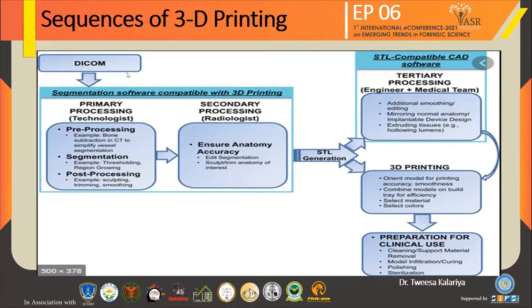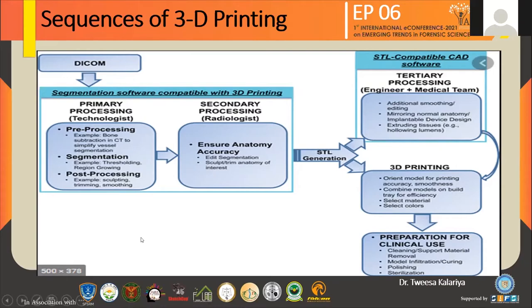STL compatible CAD-CAM software: the necessary process is done by the engineering or medical team, including additional smoothing and editing, mirroring the normal anatomy, implantable device design, and extruding tissues such as hollowing the lumens. 3D printing steps include orienting the model for printing accuracy, smoothening, combining the models on the build tray for efficiency, selecting materials and colors, preparation for clinical use, cleaning and support material removal, model infiltration, curing, polishing, and sterilization.